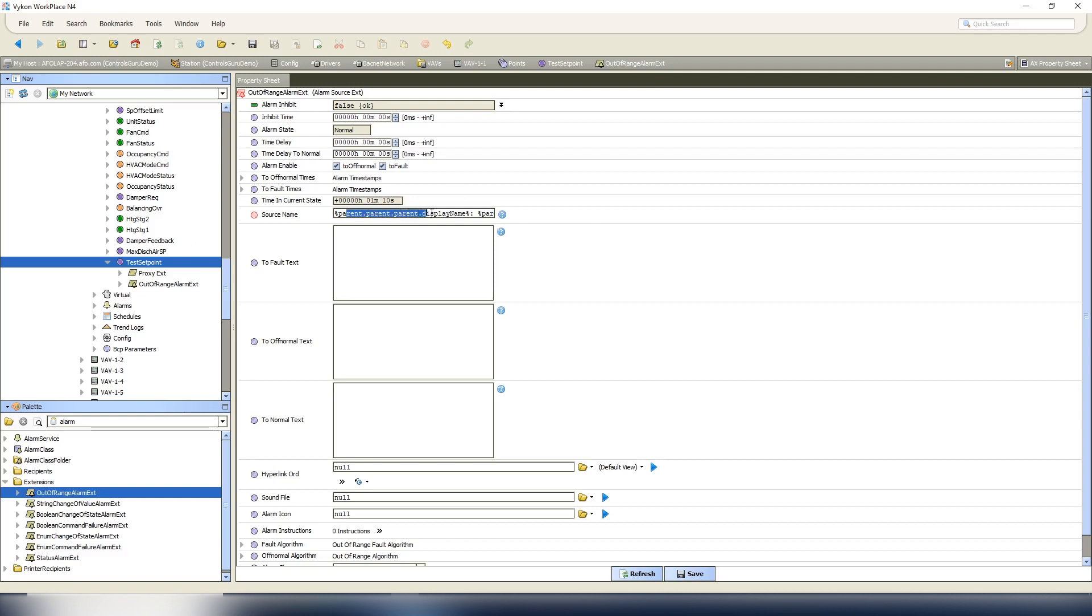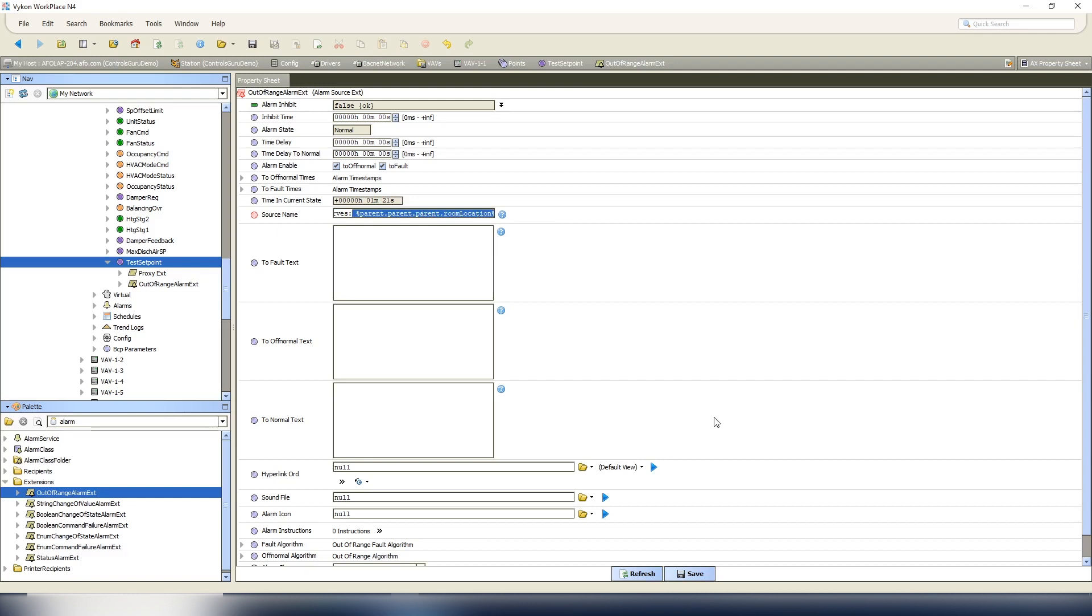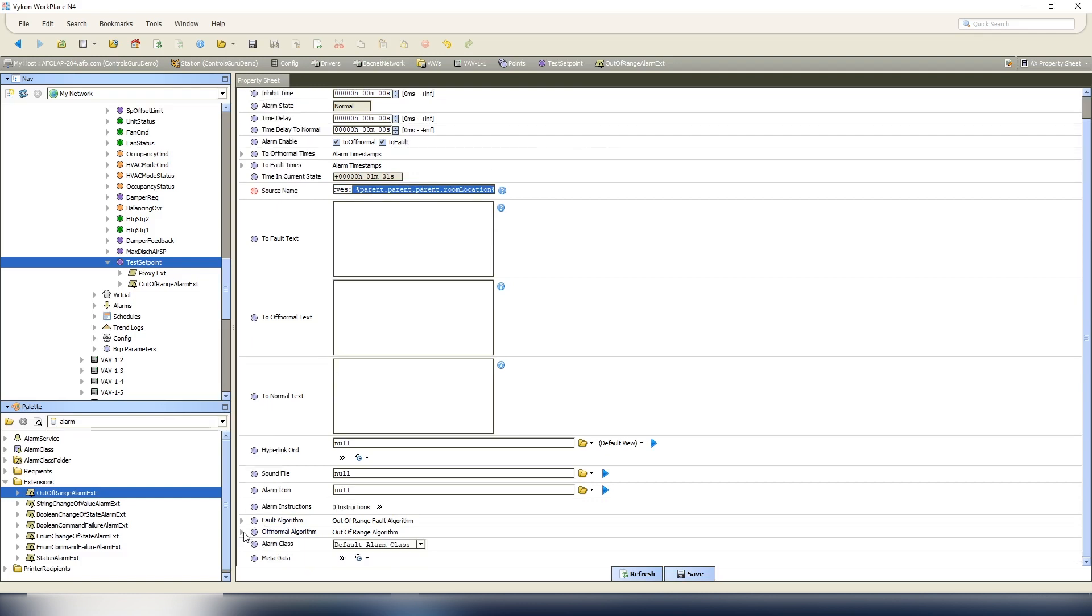So now the way this is going to read is VAV 1-1 colon test set point space dash space zone serves, and then it should say the room location name. Now that we have this in our source name, we can do our out of off normal algorithms. Because this is going to be an out-of-range limit, so we're going to set our high limit to 80, our low limit to 60. And again, this is all preference to how you do your setups and what points you're mapping.